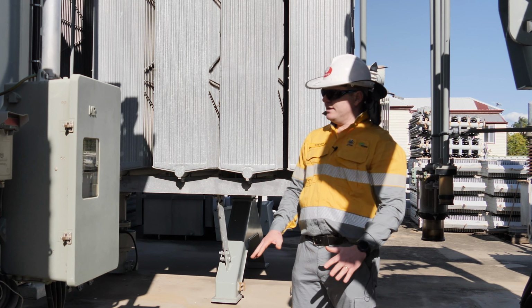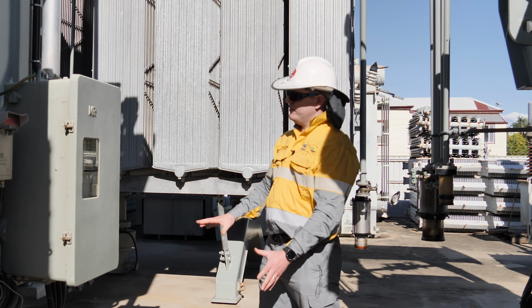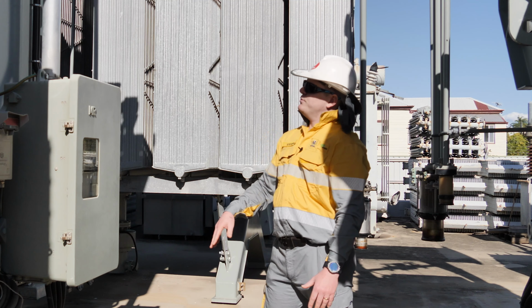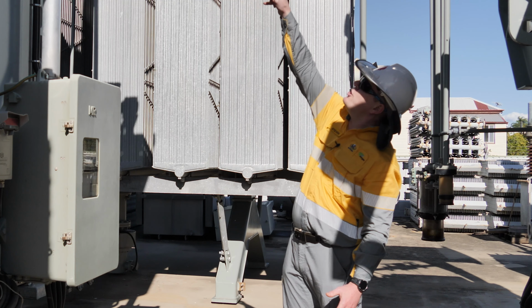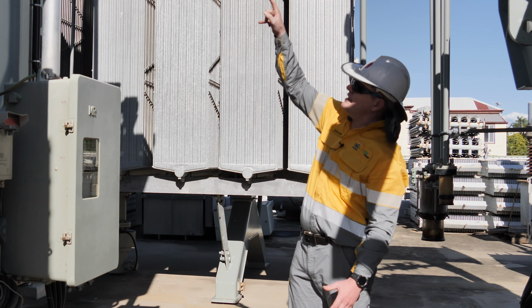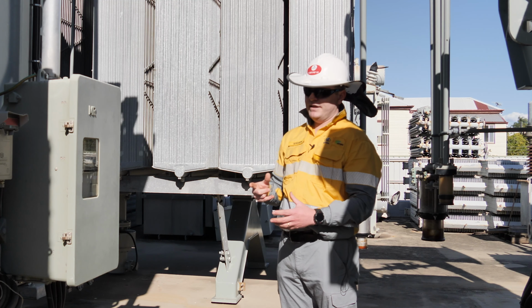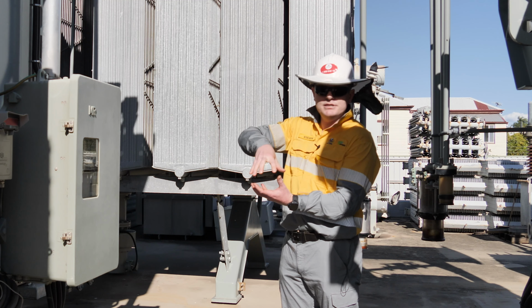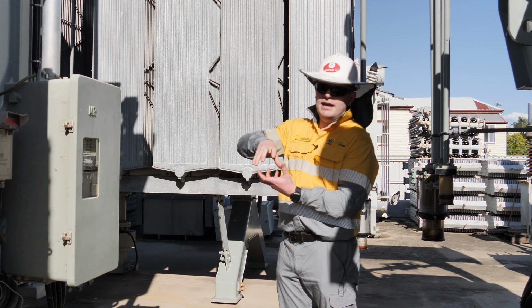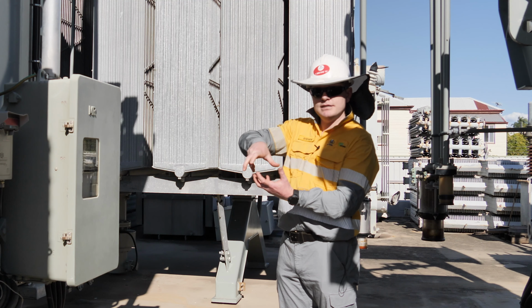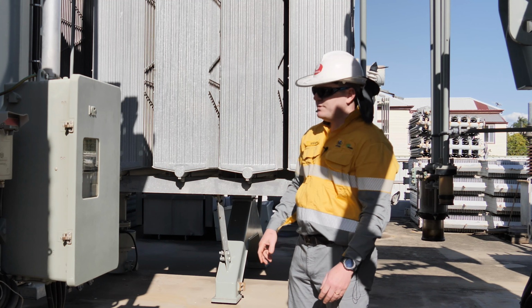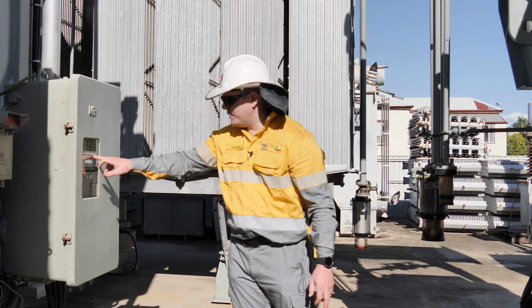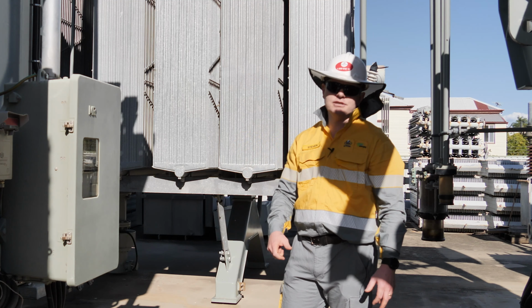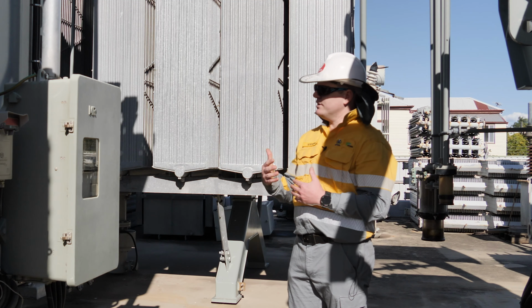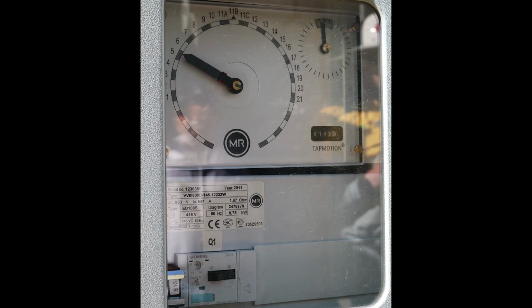So the tap changer, it's basically a motor. We have the control cubicle here, and we have a shaft that goes up towards the top of the main tank, and what that motor does is it physically changes the position of some contacts in the tank, and each position of those contacts relates to a winding ratio. This particular tap changer has 21 different tap positions, and that, as I said before, can be used to compensate for changes in either the primary or secondary voltage on the transformer.